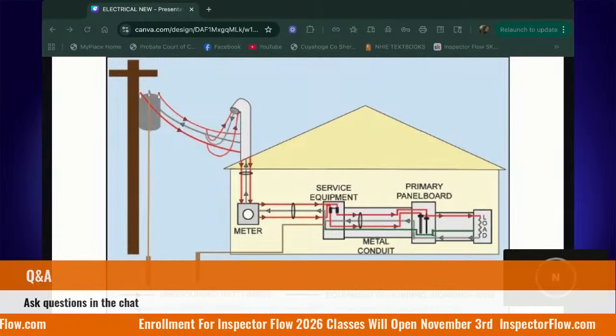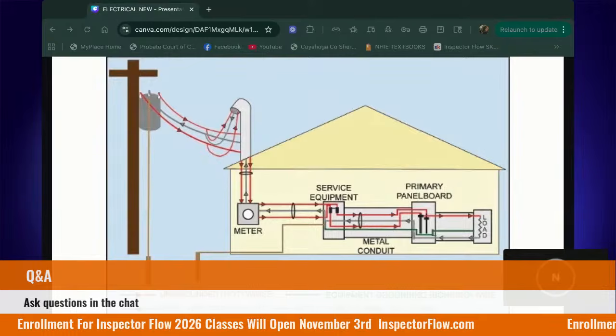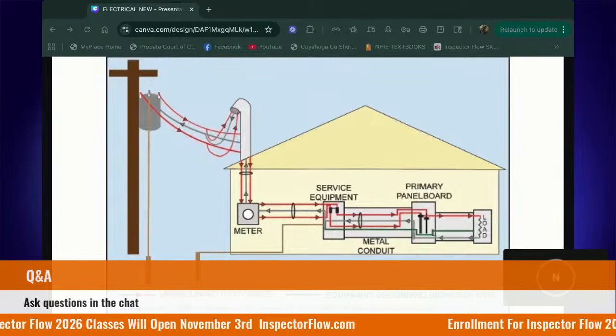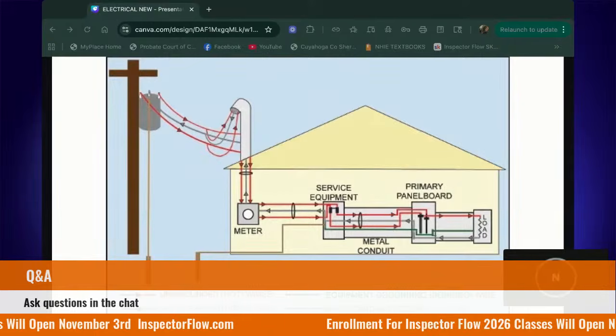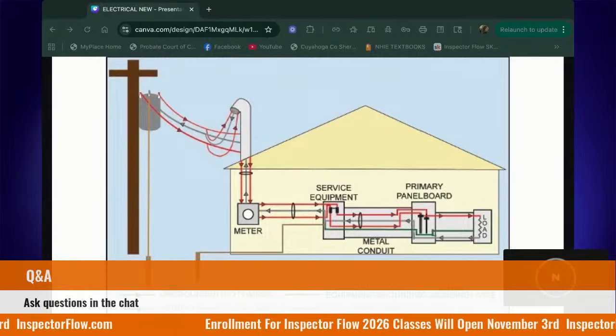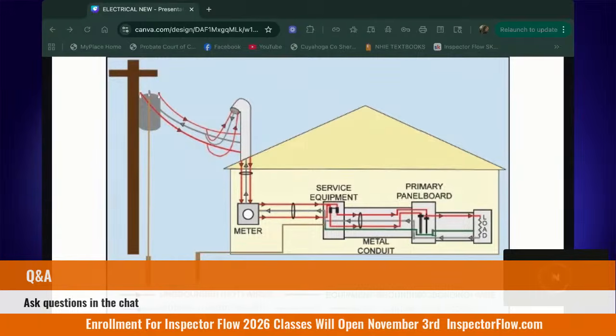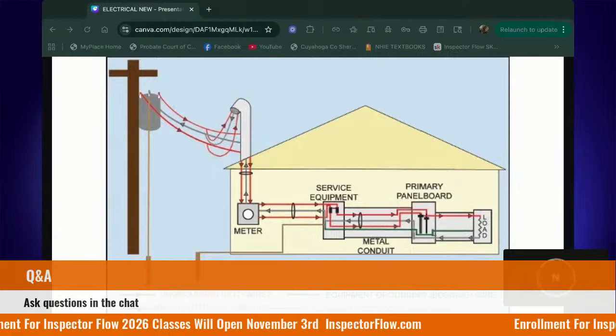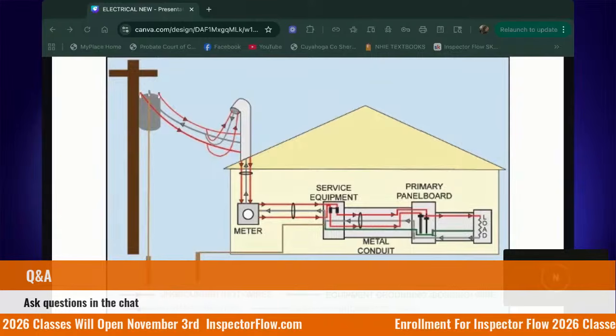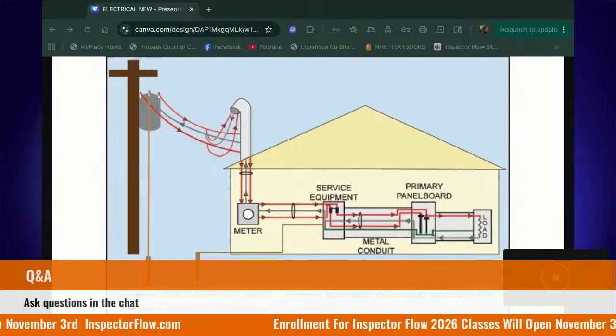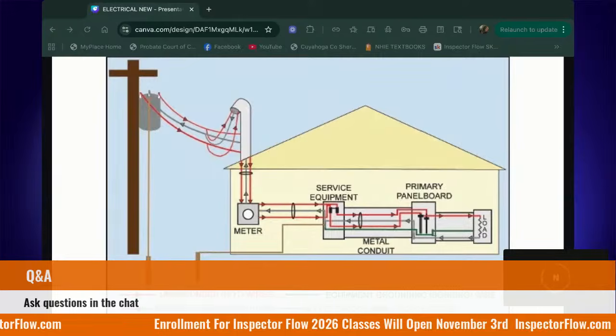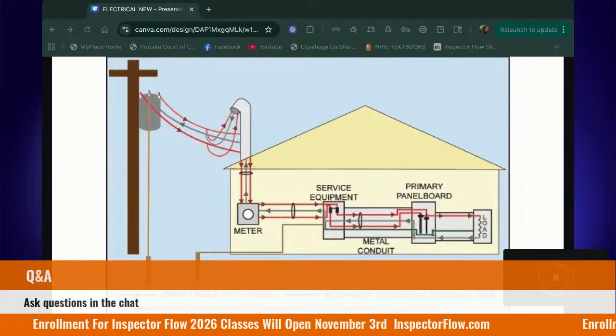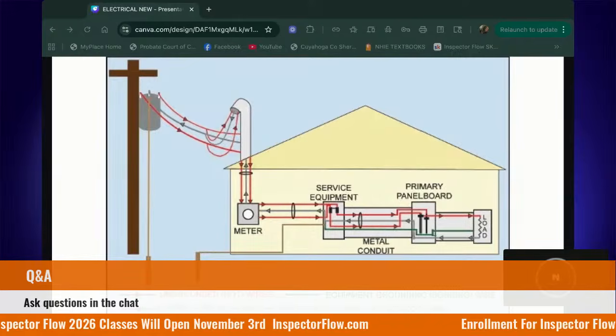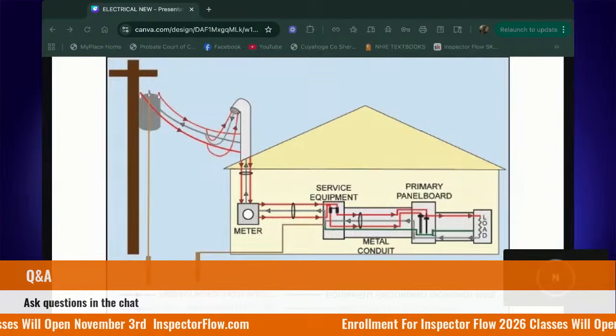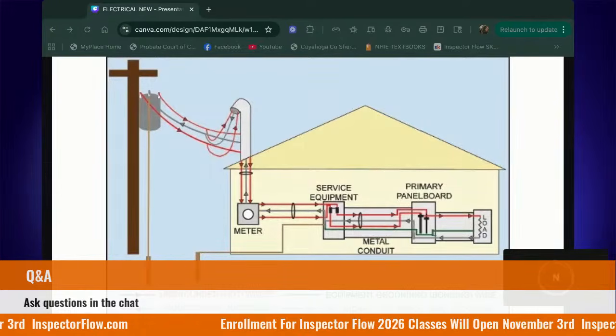Okay, so our GEC, you told me on one end is connected to the GE, or grounding electrode, that's outside. And then the other side, you say the system. I agree. You say a bus bar. I agree. Which bus bar? Is it the neutral bus bar? Is it the grounding bus? Grounded bus bar.